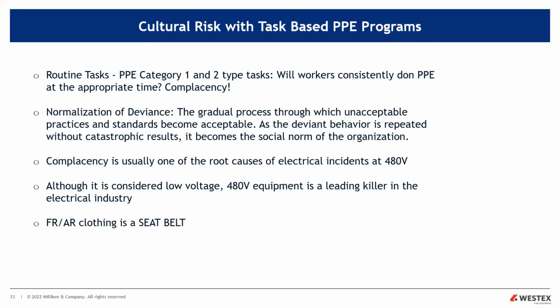The seatbelt, now think about this analogy. It really doesn't work for a task-based scenario as a protective measure. Let's say you're taking a quick trip to the store to get some milk and you're coming back. It's a quick trip. So you're not going to put your seatbelt on. What can happen? It's only a few blocks away. Well, some guy that's drunk comes over the center line and hits you. Hey, it's too late to don that seatbelt. Just like if you're doing a routine task on 480, just doing some quick thing. At the end of the day, don't put the PPE on. An arc flash happens. Too late to don the PPE. It's just too late. Now, let's look at the two types of PPE from a preventative measure standpoint.